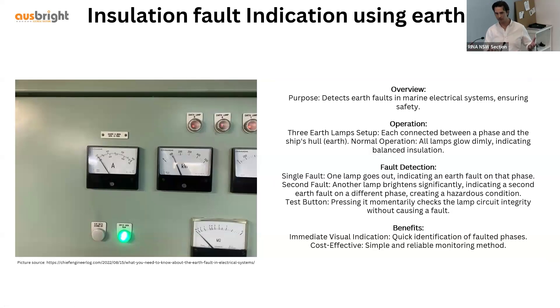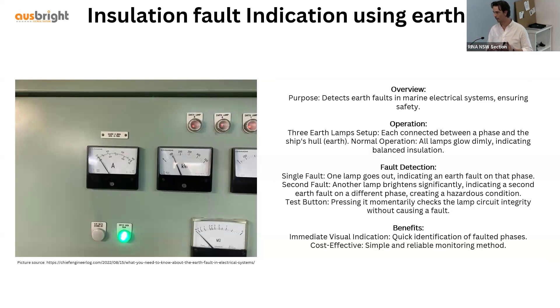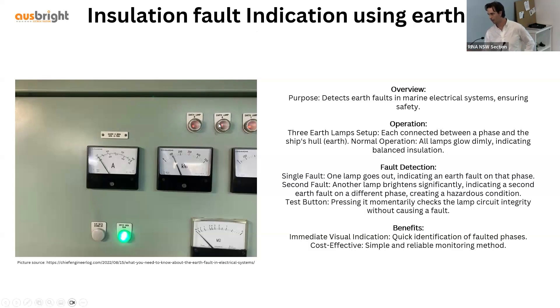Now we've learned about an IT system, I'm going to move on to the insulation monitoring devices that have to be employed to help monitor Earth faults — ensuring that if you do have an Earth fault, you know about it and can rectify it before a second Earth fault can occur. The first insulation monitoring devices were simply three LED lamps, still used today, however they're not very sophisticated.